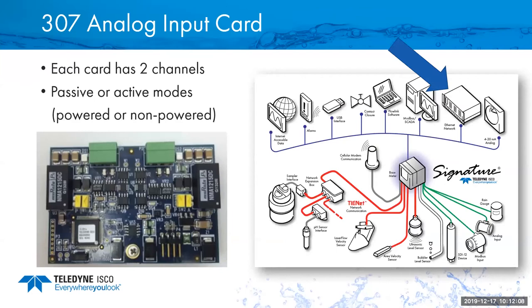The 307 analog input is a way of bringing a 4 to 20 signal into the signature meter. So we could connect up to, say, a mag meter or some other 4 to 20 output of a SCADA system and bring that into the signature meter to pace a sampler, store the data, and perform functions with a 304 contact closure.